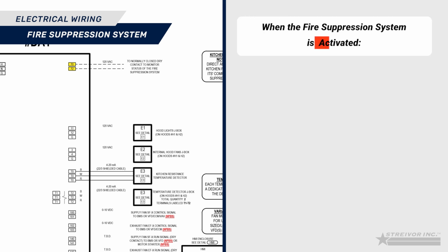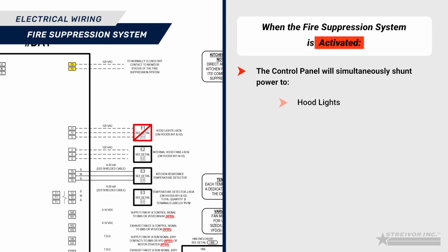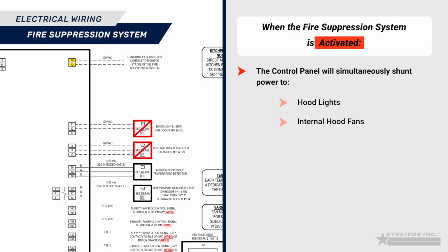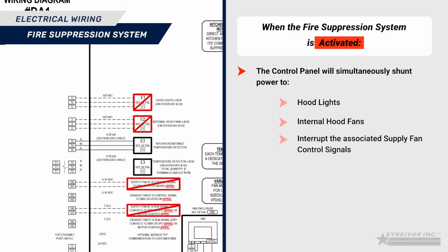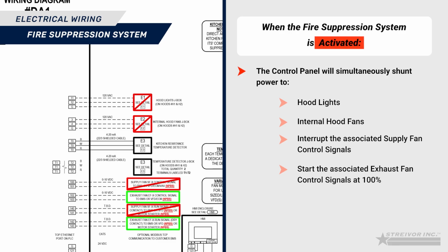When the fire suppression system is activated, the control panel will simultaneously shunt power to the hood lights, internal hood fans, interrupt the associated supply fan control signals, start the associated exhaust fan control signals at 100%, and apply 120 VAC power to the normally open shunt terminals.